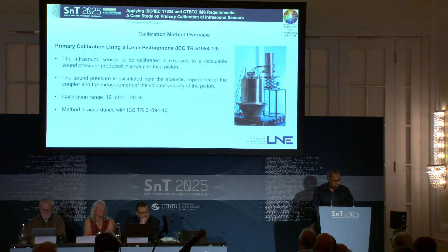So a few words first regarding the new calibration service. It's a primary calibration of infrasound microphones using the laser pistonphone, a calculable pistonphone. The core of the method is a rigid piston, which generates a sound pressure inside a cavity. This is achieved by measuring the volume velocity of the piston using a laser interferometer, combined with an accurate knowledge of the acoustic impedance. Currently we cover the range of 10 millihertz to 20 hertz, and the method is fully compliant with this IEC technical report, which was developed just after the Infra-AUV project.